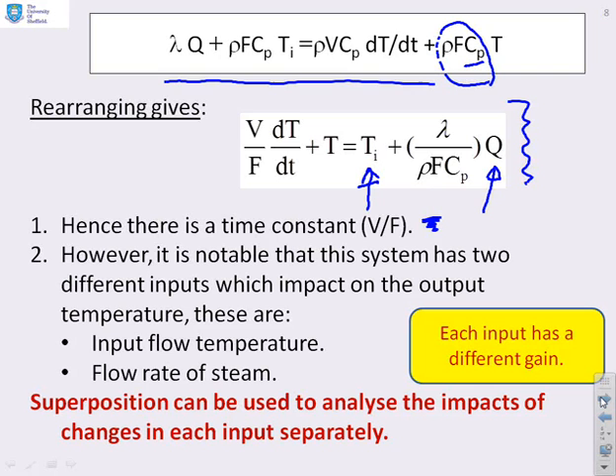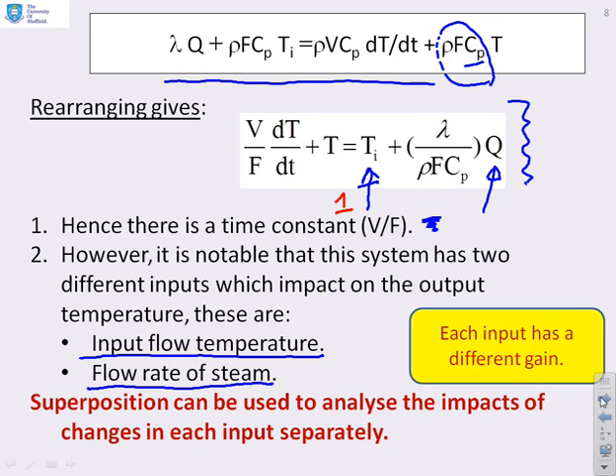One of those inputs is the temperature of the input flow, and the second input is the flow rate of steam, which is what's supplying the heat. Because this is a linear model we can use superposition and analyse the impacts of each of these separately. You'll also notice that each input has a different gain. The input temperature has an effective gain of 1 — in other words, in the steady state the output flow temperature would match the input flow temperature if there was no heating, which is what you would expect: T equals T_i. There is also a gain associated with the heating: as you increase the steam flow and therefore the energy into the heater, the output temperature increases.